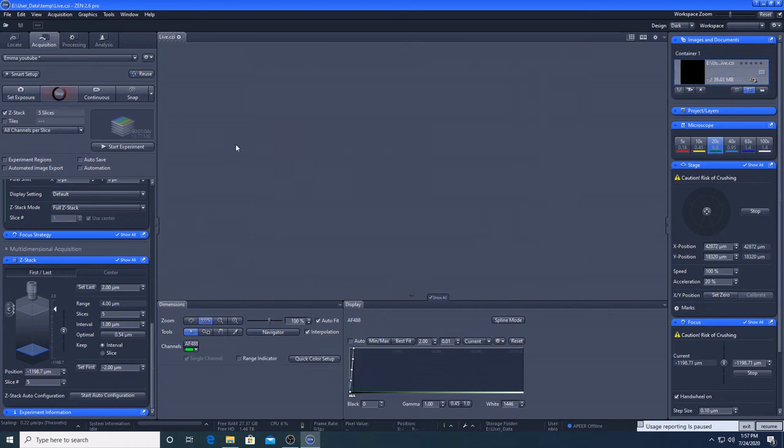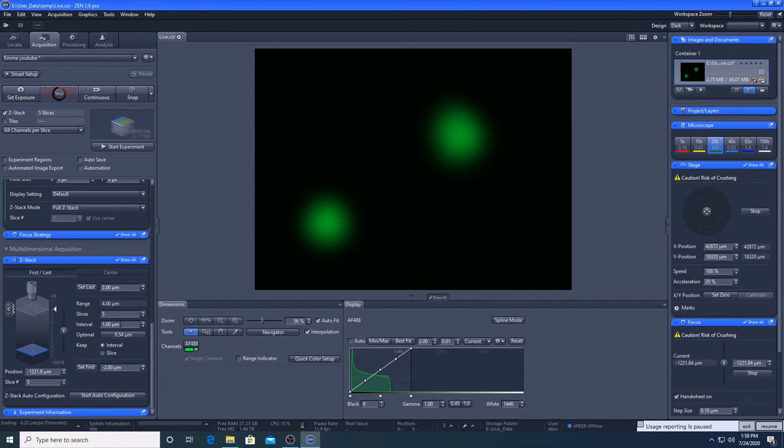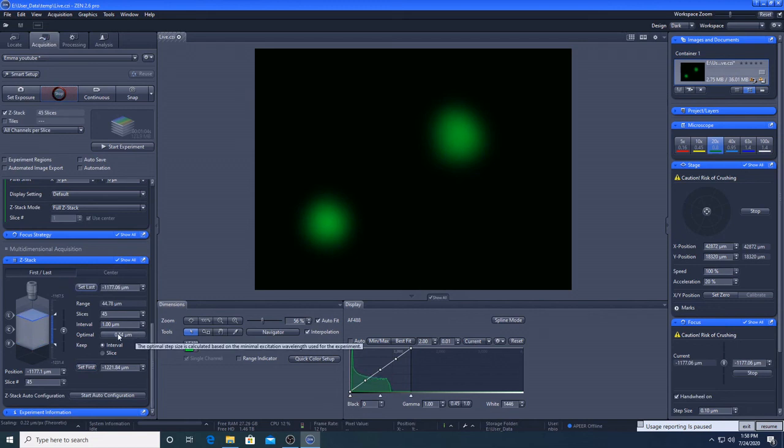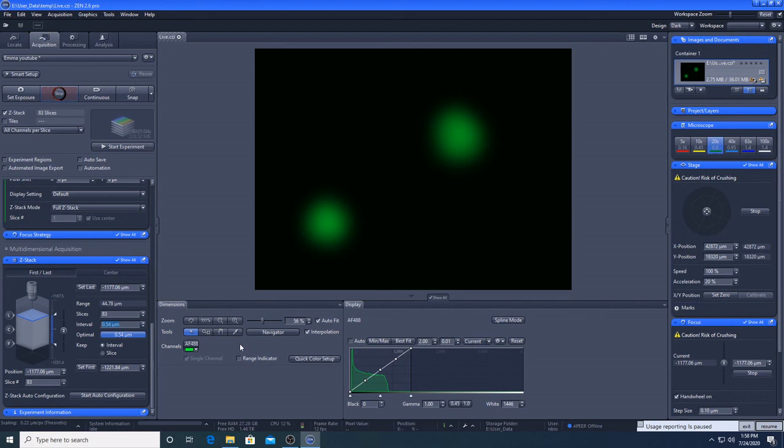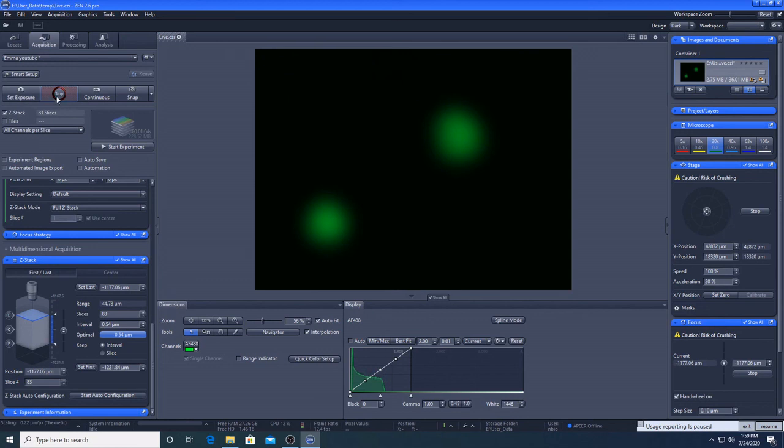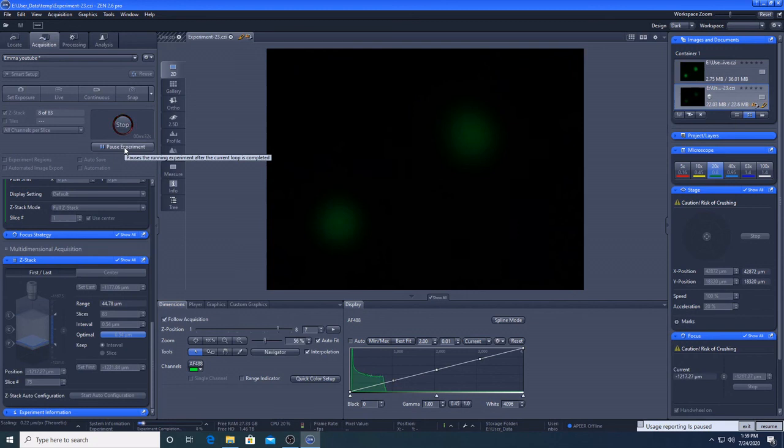So if I want to take a z-stack on here, so I'm going to go live and scroll through one way and then I'm going to say set that as first. Doesn't matter which way I go. So I'm just going slightly out of focus on me and I'm going to set this one as last. So if I want to optimize it to Nyquist, click this and that recommends setting 83 slices. Which because our exposure time is quite short that's not too bad. If I wanted to change that I could have a different interval or I could say I only want the interval to be one and then I take less slices which would take less time. Obviously I'm just going to stick with the optimal one for here just to show you how that will look. And so I'm going to press start experiment. It's just going to take us through the sample.